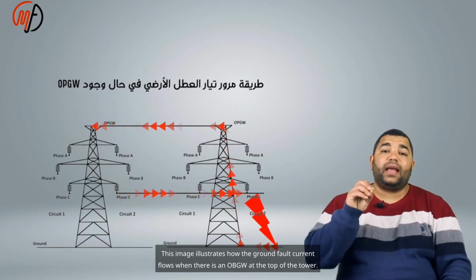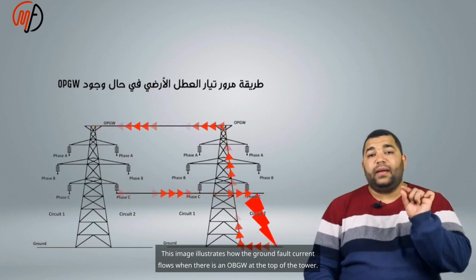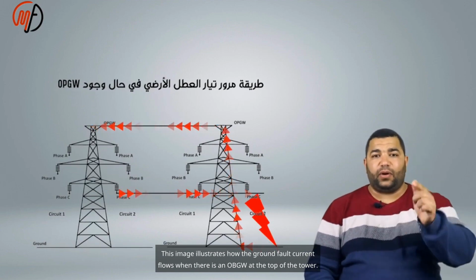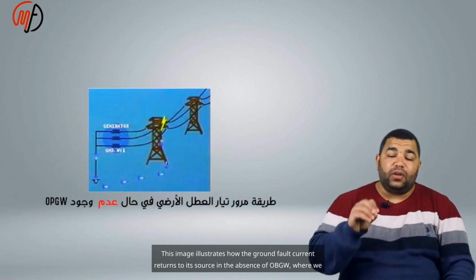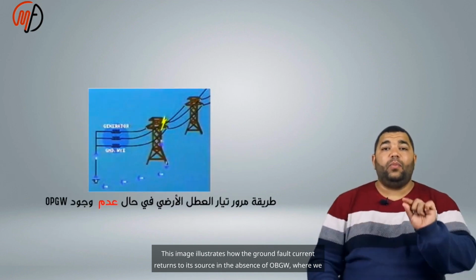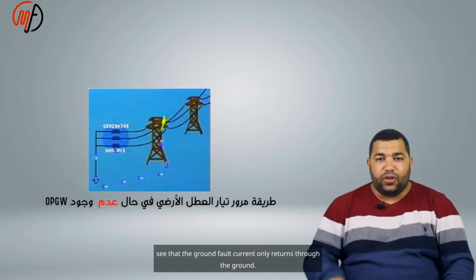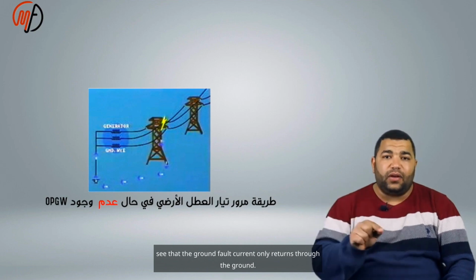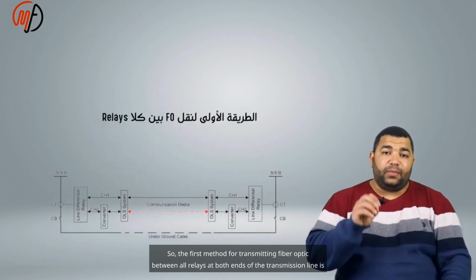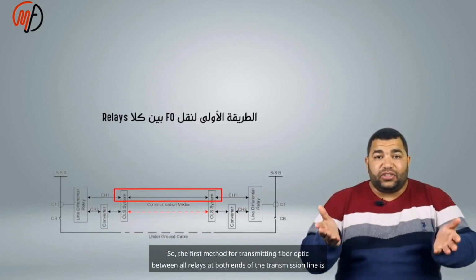This image illustrates how the ground fault current flows when there is an OPGW at the top of the tower. This image illustrates how the ground fault current returns to its source in the absence of OPGW, where we see that the ground fault current only returns through the ground.